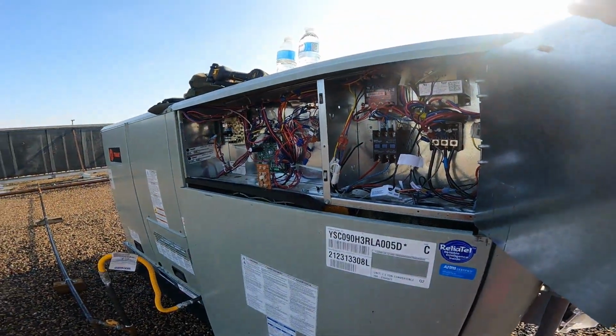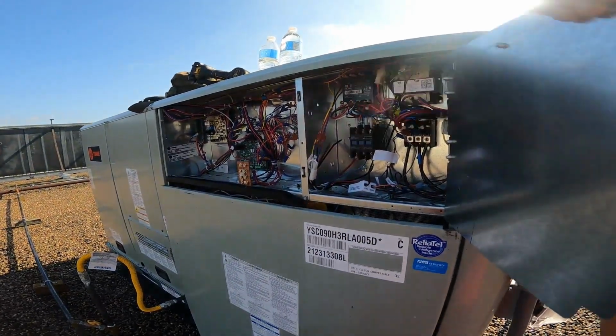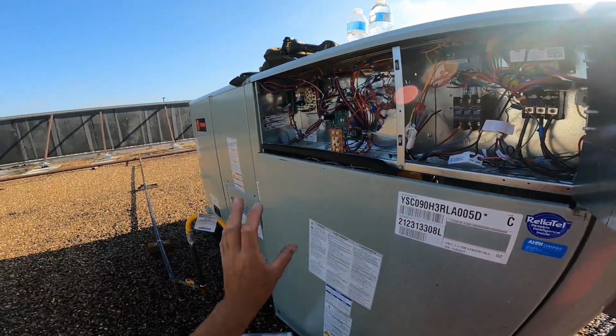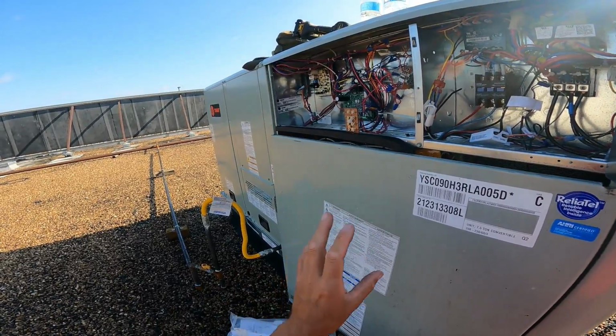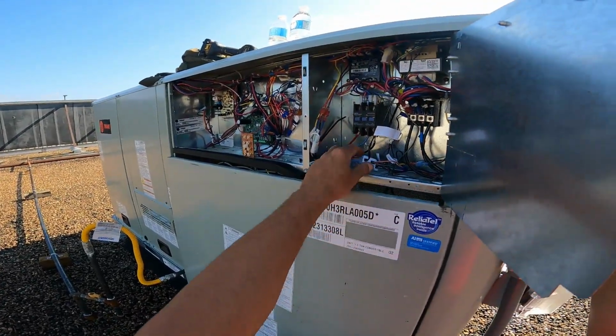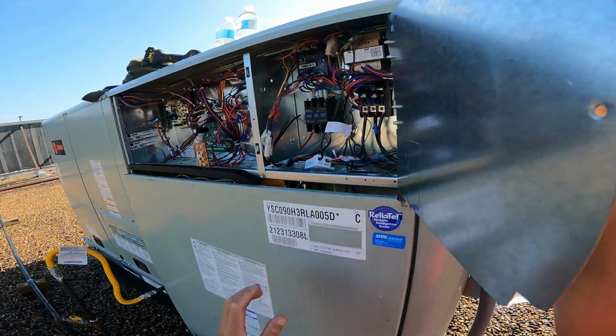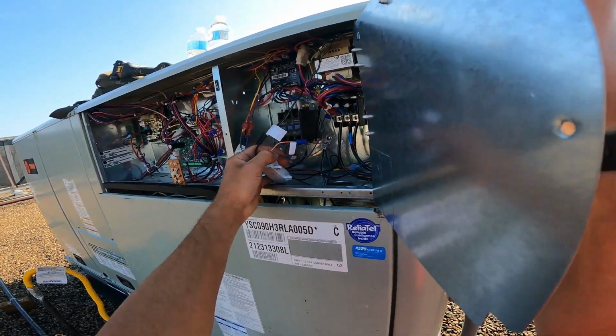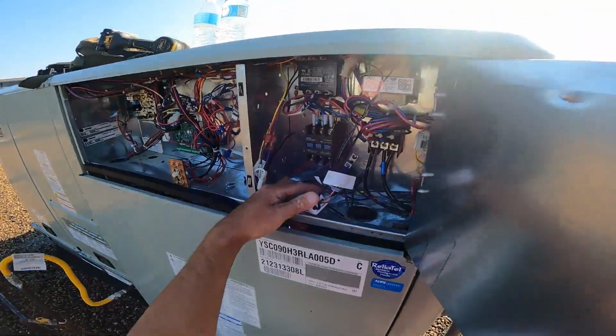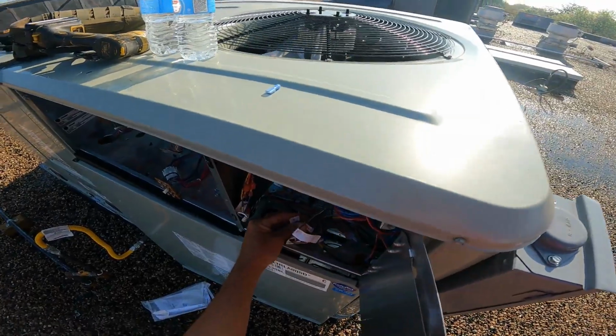So now we have to think about what we've done between the original startup and the time they came out last. So they could have put this in. Possible, especially if they didn't wire it right. What did they wire it to? Common, and it should have been normally closed. Yep, they wired that correctly.